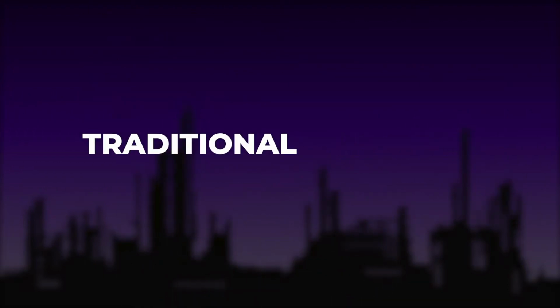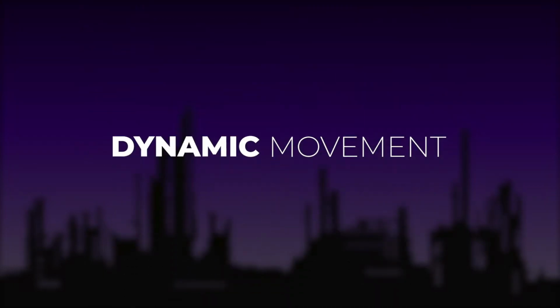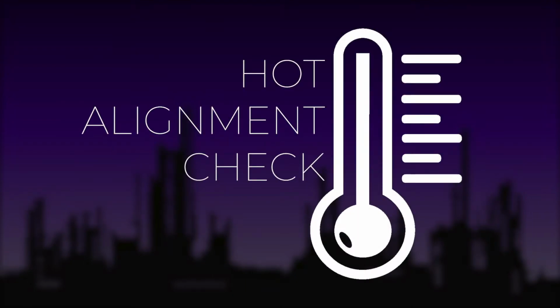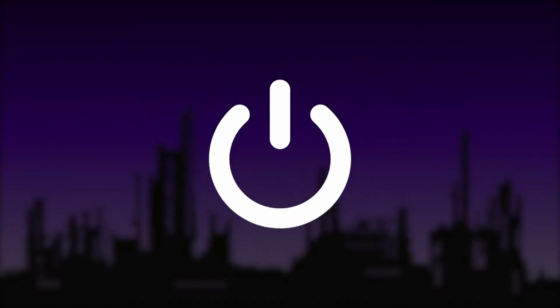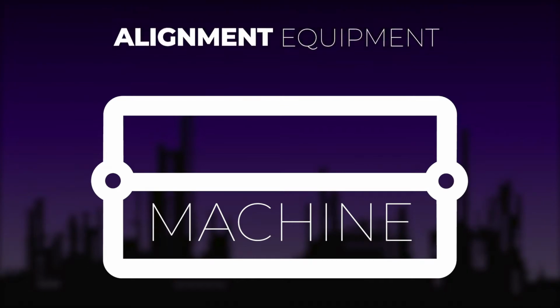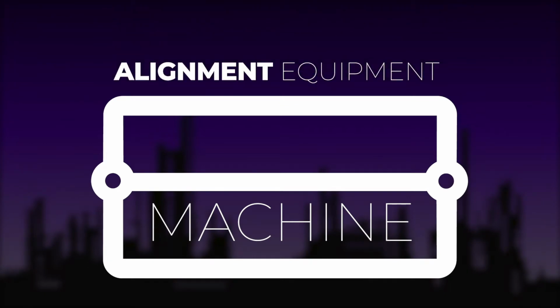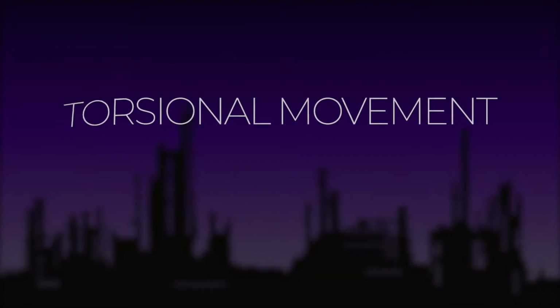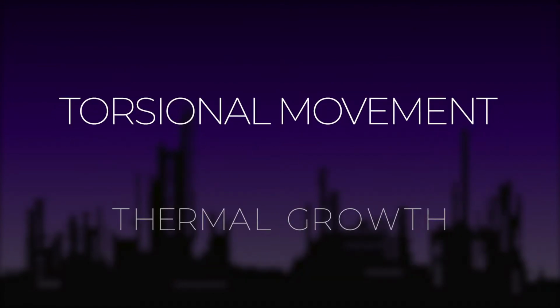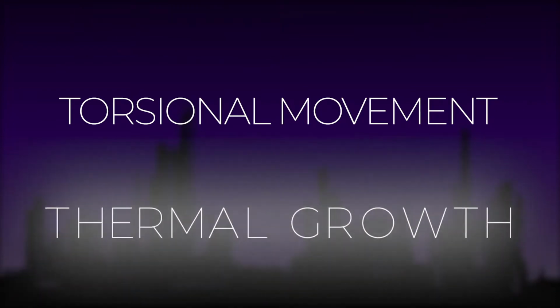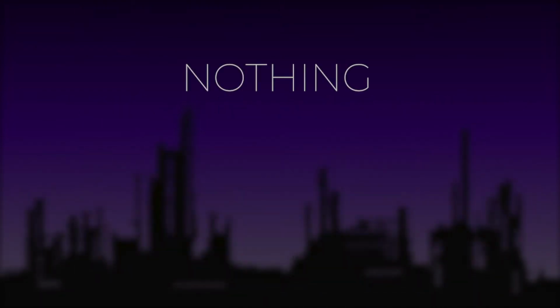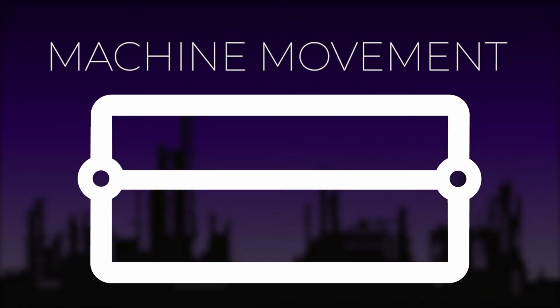turbines. There are a few traditional methods that we use instead of conducting a dynamic movement study. One of these is a hot alignment check. With a hot alignment check, we'll shut the machine down, lock out and tag out the machine, put all our alignment equipment on as quickly as possible, and then take a set of readings. In the time we do this, we've lost all the torsional movement and some of the thermal growth that has occurred on the machine.